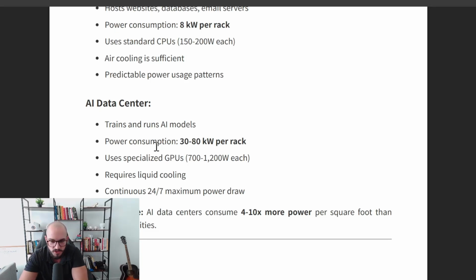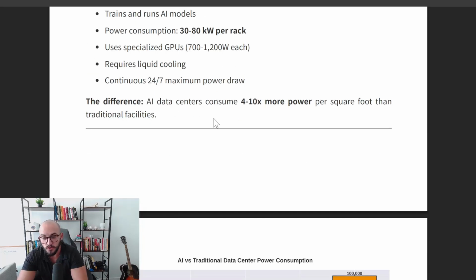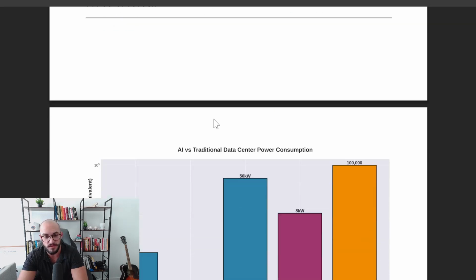Power consumption can typically be 30 to 80 kilowatts per rack, using specialized GPUs that require liquid cooling. You're consuming so much power and generating so much heat that liquid cooling is the only way to keep it operational, so you can't use that air design. Liquid cooling requires a significant amount of infrastructure upgrades. AI data centers consume 4 to 10 times the power per square foot compared to traditional facilities, and that might change.